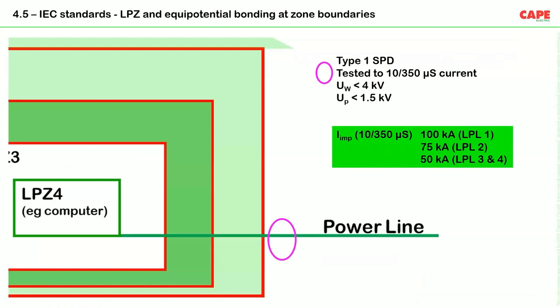For Type 1 SPDs at the building entrance: in LPL1, expected impulse current is 100 kA (50% of 200 kA); in LPL2, it is 75 kA (50% of 150 kA); in LPL3 and LPL4, it is 50 kA (50% of 100 kA). In each case, 50% of the lightning energy dissipates into the ground and the remaining 50% returns into the building through power lines via SPDs.